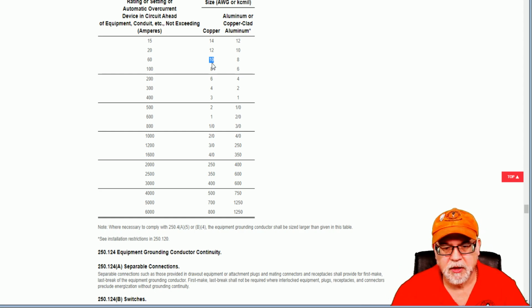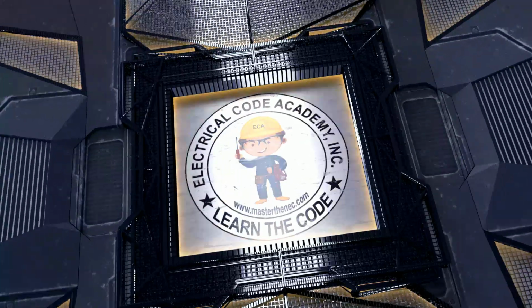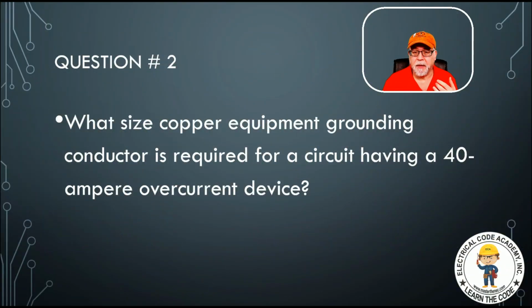Okay, so we go back to the question. What size copper equipment grounding conductor for this 40 ampere overcurrent device? 10 gauge copper. Just that simple. Just remember that just because your overcurrent device is missing from the list, you go to the next size of overcurrent device that is in that list. Okay. All right. Next question.